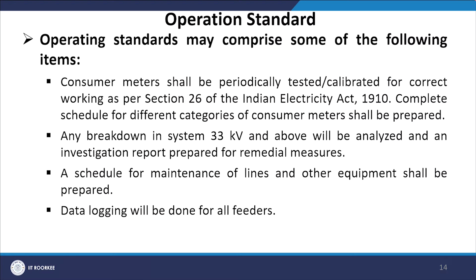Operating standards include: consumer meters shall be periodically tested and calibrated as per Section 26 of the Indian Electricity Act 1910; a complete schedule for different categories of consumer meters shall be prepared; any breakdown at 33 kV and above will be analyzed with an investigation report for remedial measures; a maintenance schedule for lines and equipment shall be prepared; and data logging will be done at all feeders.